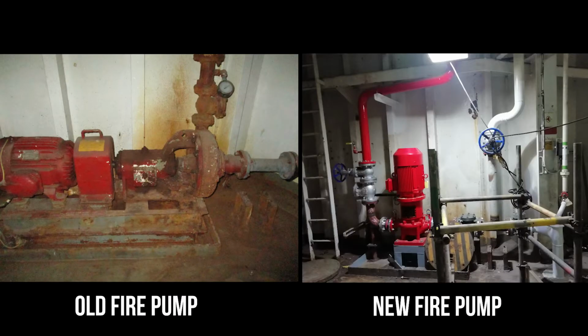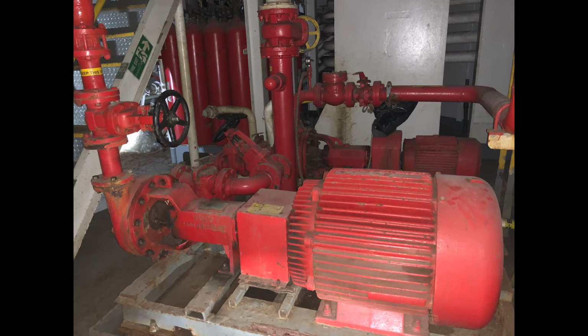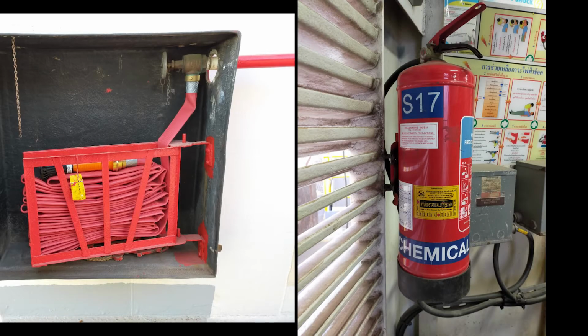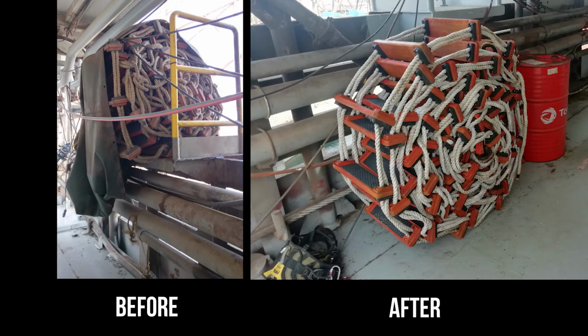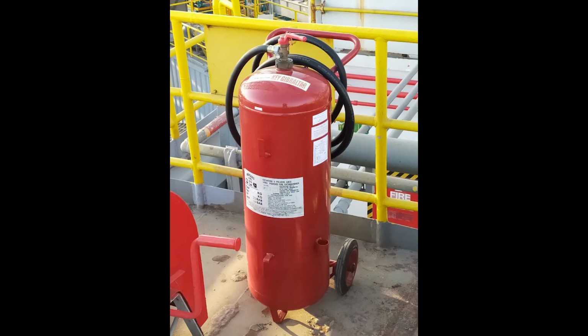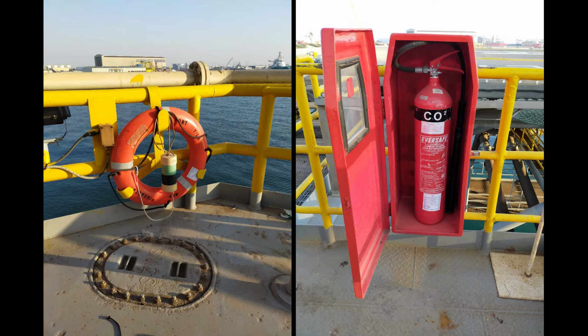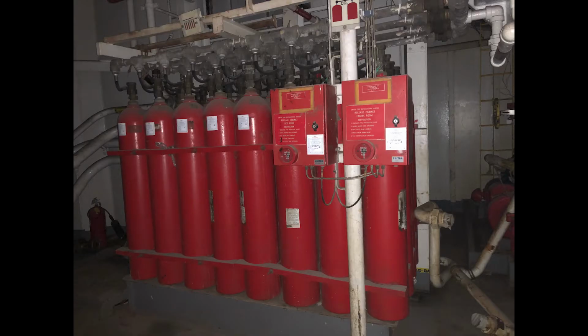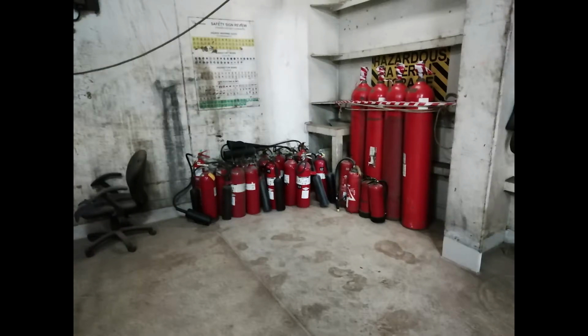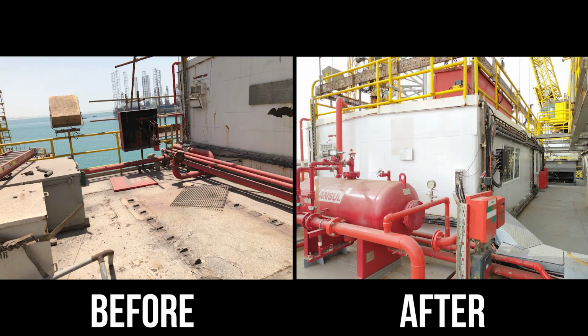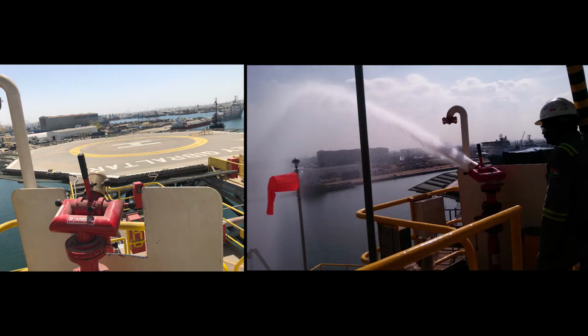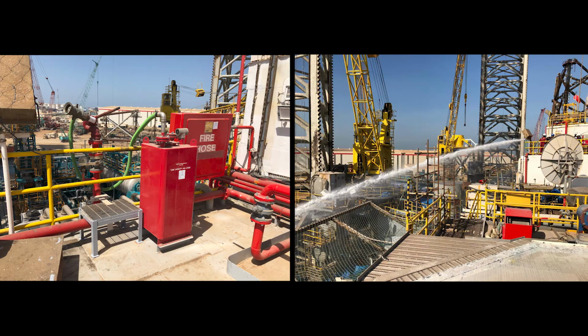One existing fire pump is replaced with new, and other pumps were overhauled. The existing firefighting and life-saving appliances were serviced or replaced with new, as per SOLAS rules. The existing CO2 system is refurbished and recertified. New helideck foam skid and monitors were installed and tested. 4 new foam monitors were added for process-side firefighting as per the HAZOP study.